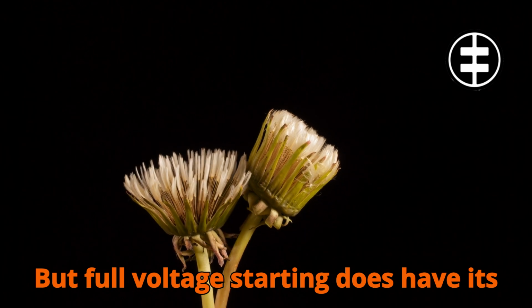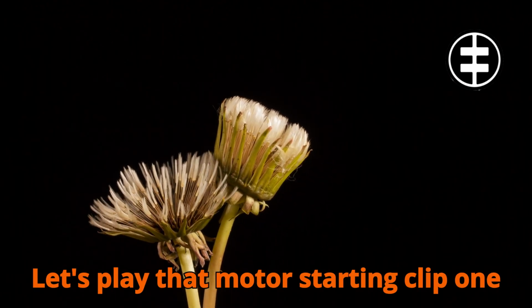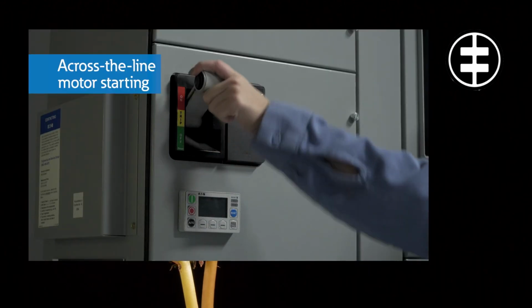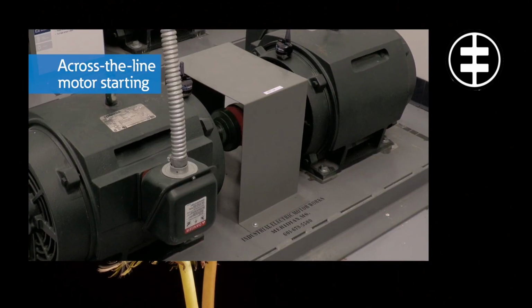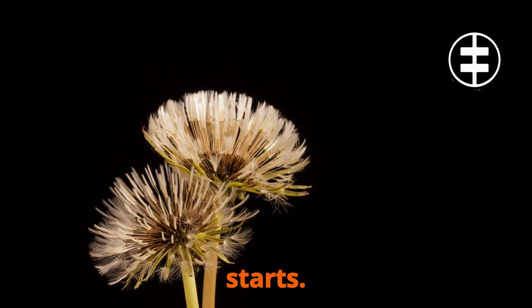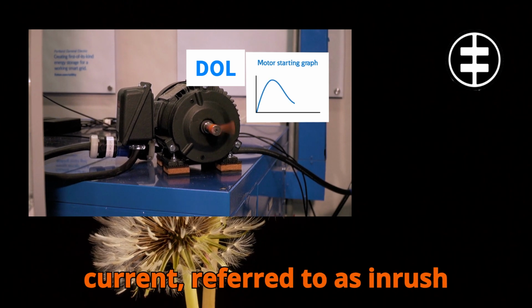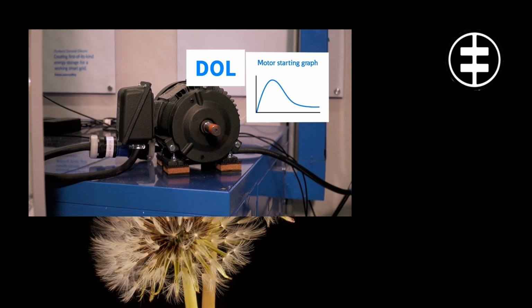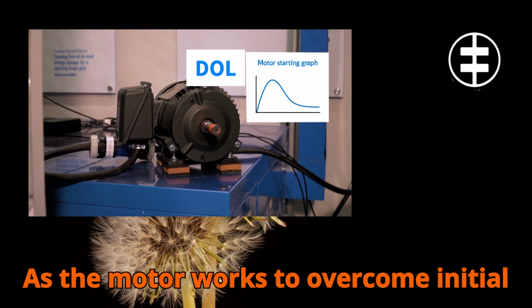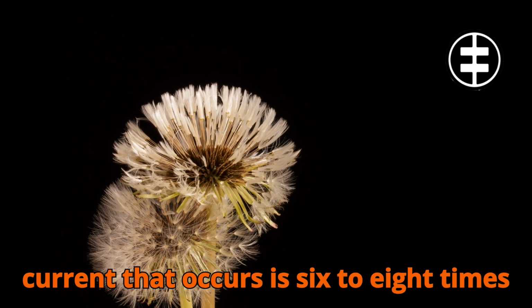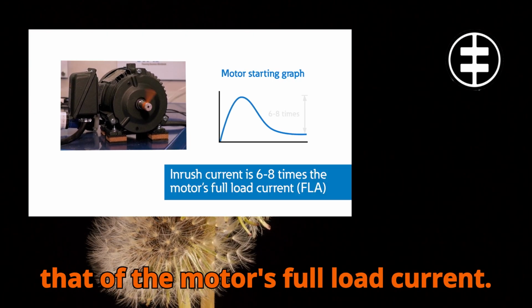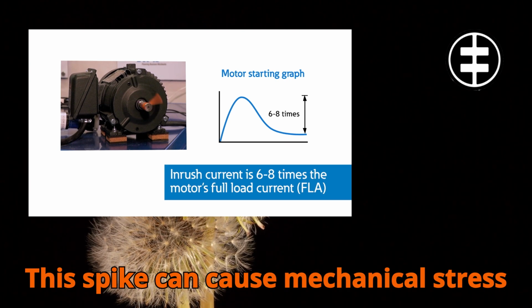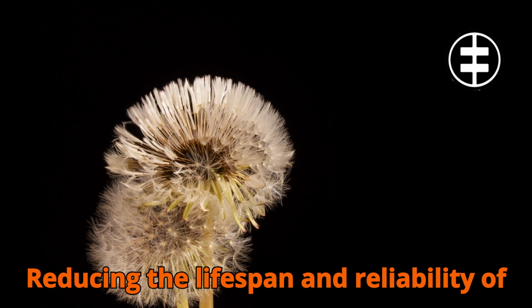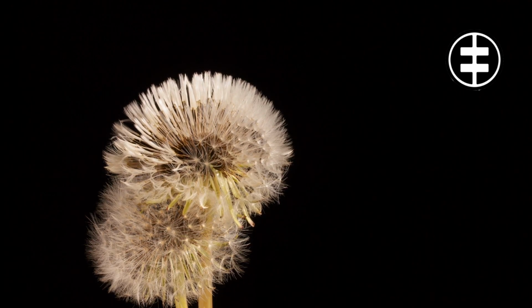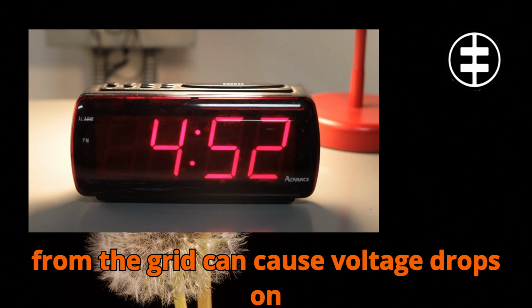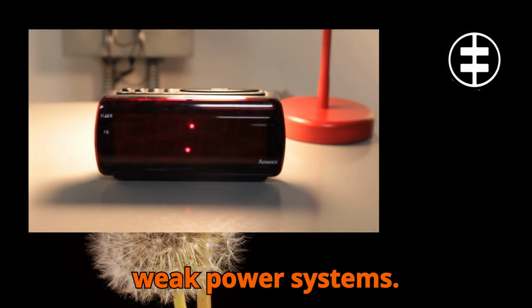But full-voltage starting does have its drawbacks. Let's play that motor starting clip one more time. Hear that loud hum right as the motor starts? That is a high momentary surge of current, referred to as inrush current. As the motor works to overcome initial inertia and reach full speed, the inrush current that occurs is 6 to 8 times that of the motor's full load current. This spike can cause mechanical stress and strain, reducing the lifespan and reliability of the motor. Not only that, but the excess power draw from the grid can cause voltage drops on weak power systems.